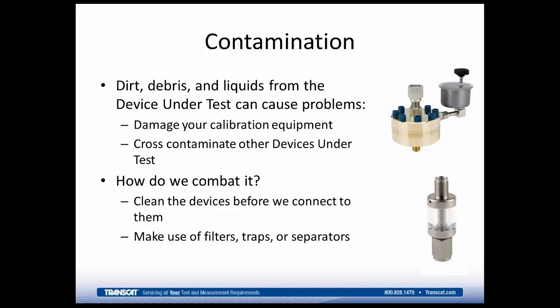Examples of filters or traps or separators can be used. Shown here at the top is an example of a separator. Here, on the bottom is where you can connect to your reference, at the top is where you can connect your device under test, and there's a diaphragm in the middle. So when you change the pressure below, it pushes up on the diaphragm and changes the pressure above, but the media never actually comes in contact with each other. This works great on a higher pressure oil system.